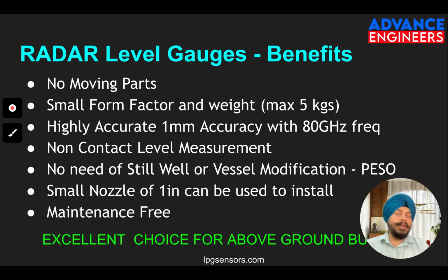So we are able to give you accuracy of 1 mm, and that is good enough. If you check your calibration charts in your vessels, they are actually calibrated not for 1 mm, but for 1 centimeter. So whether you use a servo gauge or a radar gauge, that plus minus 10 mm accuracy is good enough for you as a user.